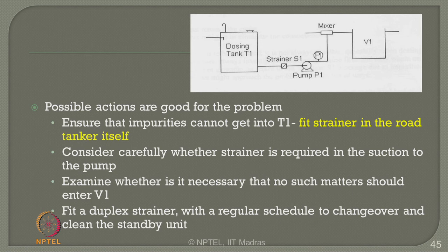Let us see for this example what are the possible actions that are required for a good problem. It ensures that impurities cannot get through T1. So, fit a strainer in the road tanker itself which supplies chemical to the tank T1. Consider carefully whether a strainer is required in the suction to the pump. Whether you can put the strainer here or not, you have to very carefully design the system for its layout. Examine whether it is necessary that no such matters should enter V1. For example, if the container V1 can allow the suspended impurities, do not put strainer S1 in this location because strainer S1 can cause no flow to this line. Fit a duplex strainer with a regular schedule to change over and clean the standby unit appropriately.